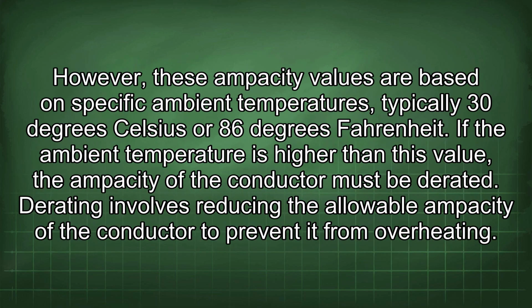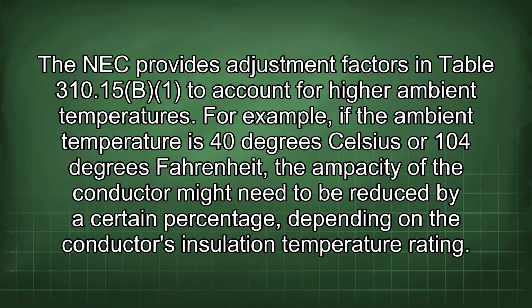However, these ampacity values are based on specific ambient temperatures, typically 30 degrees Celsius or 86 degrees Fahrenheit. If the ambient temperature is higher than this value, the ampacity of the conductor must be derated. Derating involves reducing the allowable ampacity of the conductor to prevent it from overheating. The NEC provides adjustment factors in Table 310.15 to account for higher ambient temperatures. For example, if the ambient temperature is 40 degrees Celsius or 104 degrees Fahrenheit, the ampacity of the conductor might need to be reduced by a certain percentage depending on the conductor's insulation temperature rating.